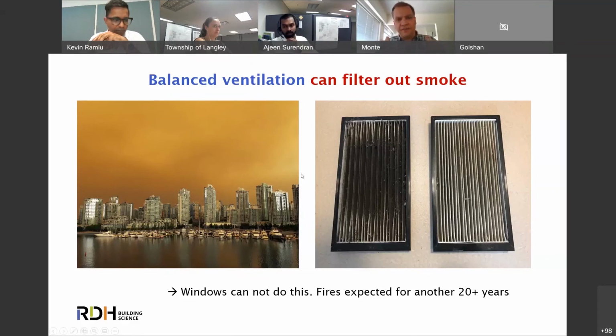Our HRVs and ERVs have filters in them. So when we bring in night ventilation through the ERV, we also filter it. When our skies are full of smoke, we can just change those filters every couple of days. All of that black stuff you see - the one on the left was right after a couple of days of wildfire smoke. The one on the right was prior, a normal dirty filter, if you want to call it that.